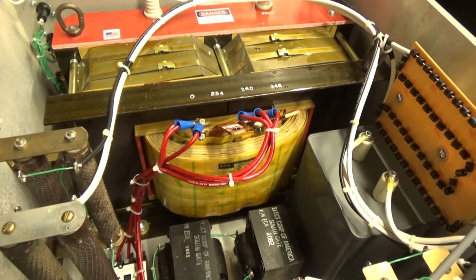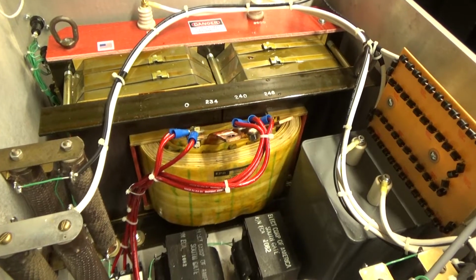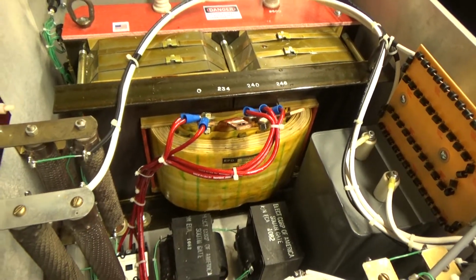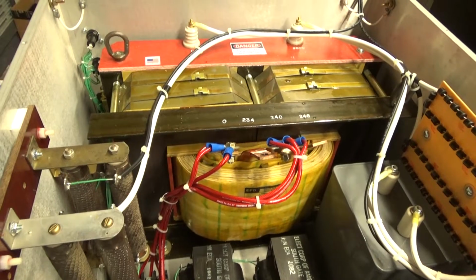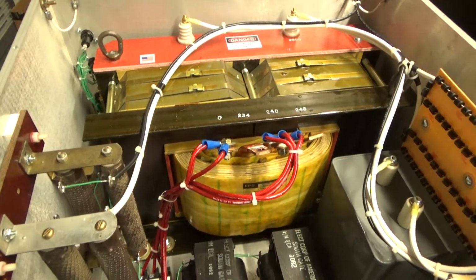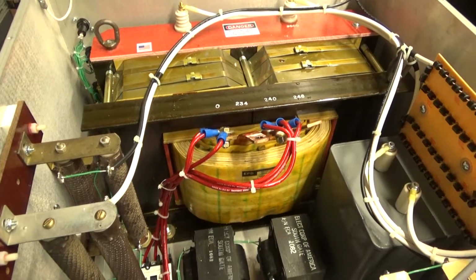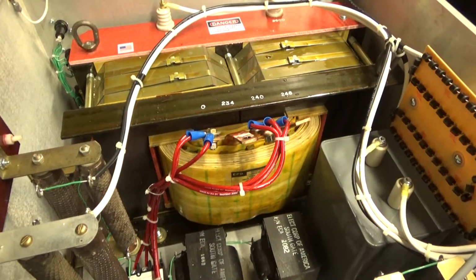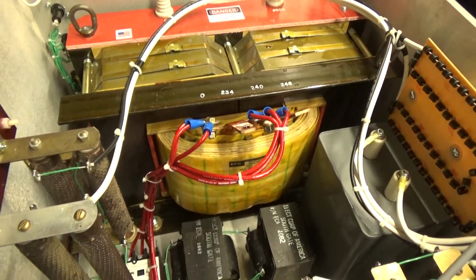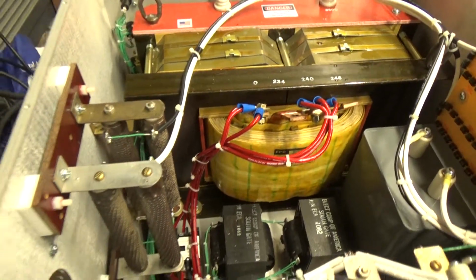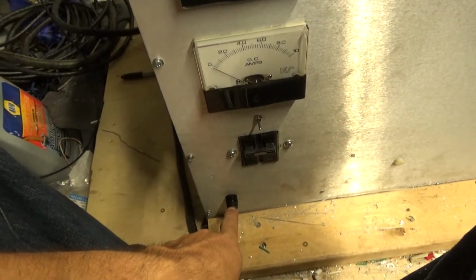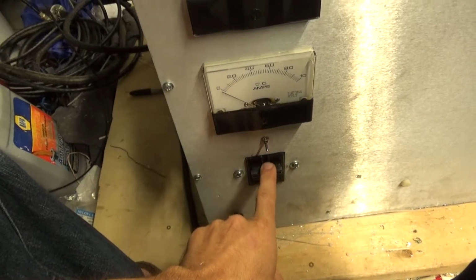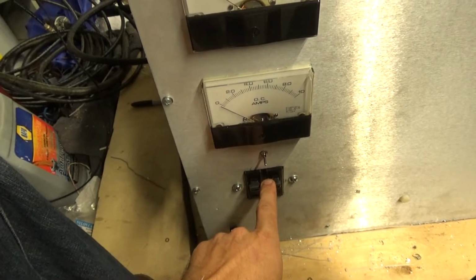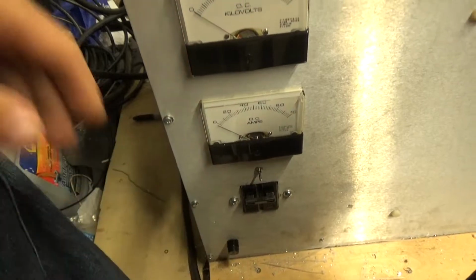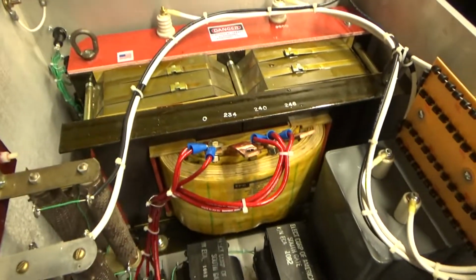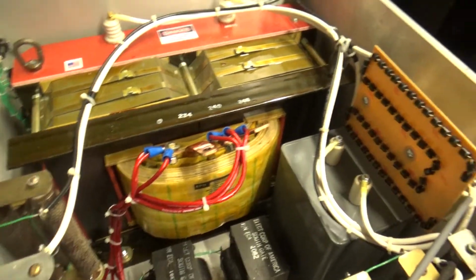It does not use a time delay. If there's a fault on the secondary, or something happened in the primary, anything after the contactor that switches the switch side of the transformer, it would pop a little 3 amp glass fuse instead of having to rely on the 125 amp line breaker. Way better than using the time delay setup.